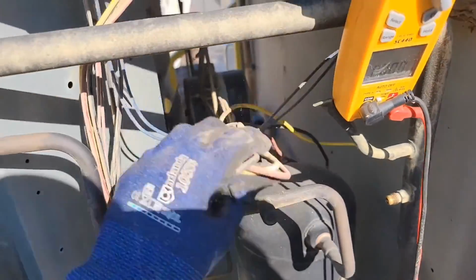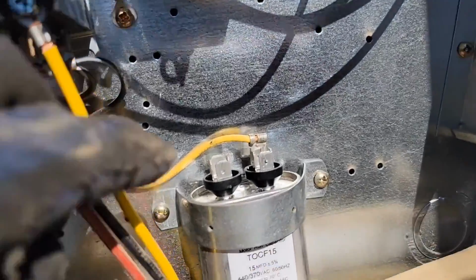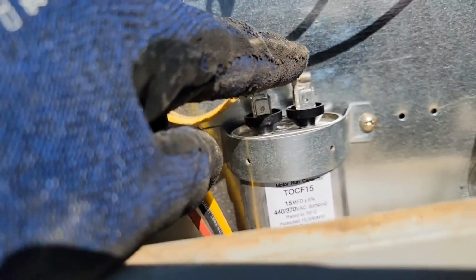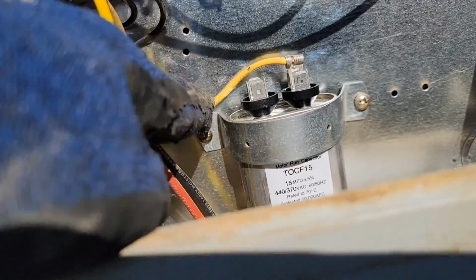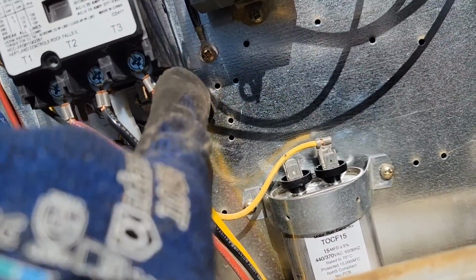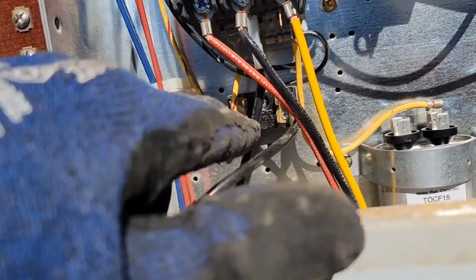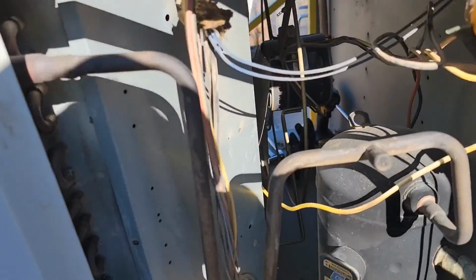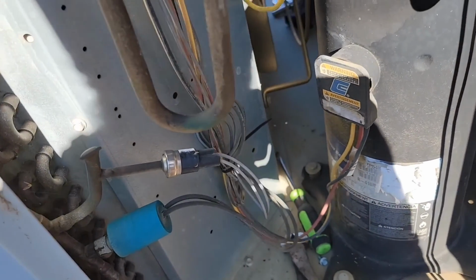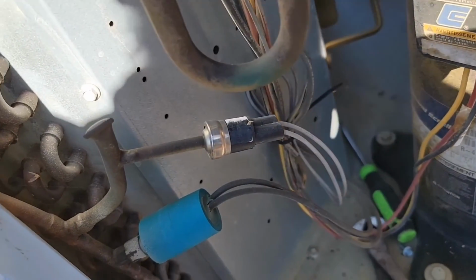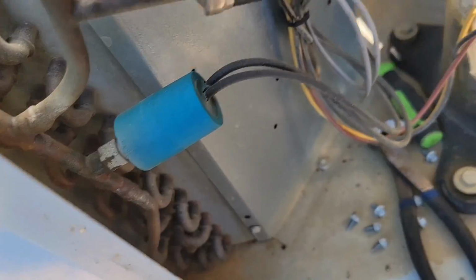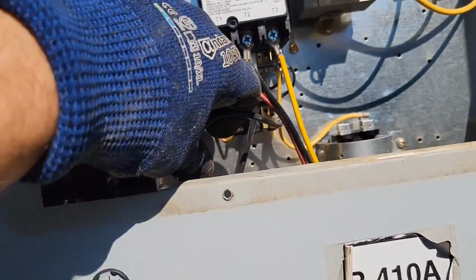If you're curious where those were connected, we had a brown to this side of the capacitor, the yellow to this side of the capacitor, and this yellow goes to one side of the leg. And then the black wire went to this terminal, and this black wire right here connects to another side of the leg, okay? So it looks like it goes down though, and I think it breaks the pressure switch, which is a little unusual.